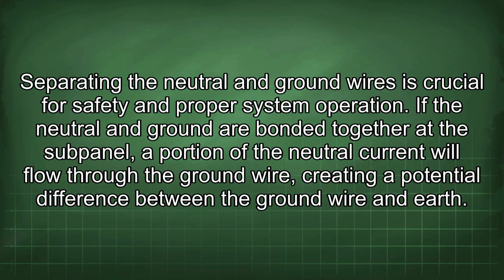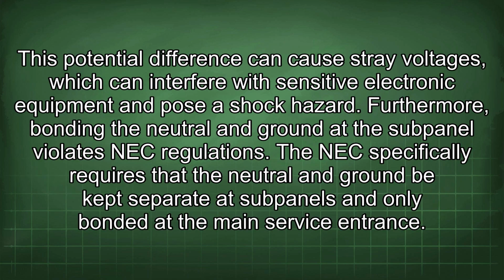Separating the neutral and ground wires is crucial for safety and proper system operation. If the neutral and ground are bonded together at the subpanel, a portion of the neutral current will flow through the ground wire, creating a potential difference between the ground wire and earth. This potential difference can cause stray voltages, which can interfere with sensitive electronic equipment and pose a shock hazard.